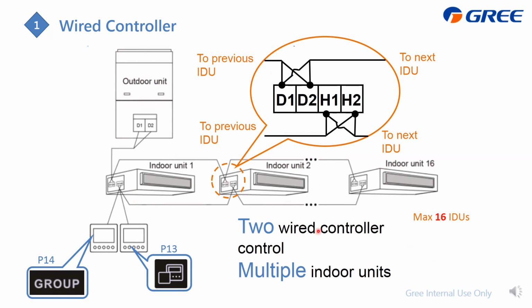Two wire controllers controlling multiple indoor units: the upper limit is also 16, and the wiring is similar to one controller for multiple units, which is series connected H1, H2, and then connect these two wire controllers at the same time to the H1, H2. Also select either one of them as the master controller at P13, and set P14, the group control quantity.